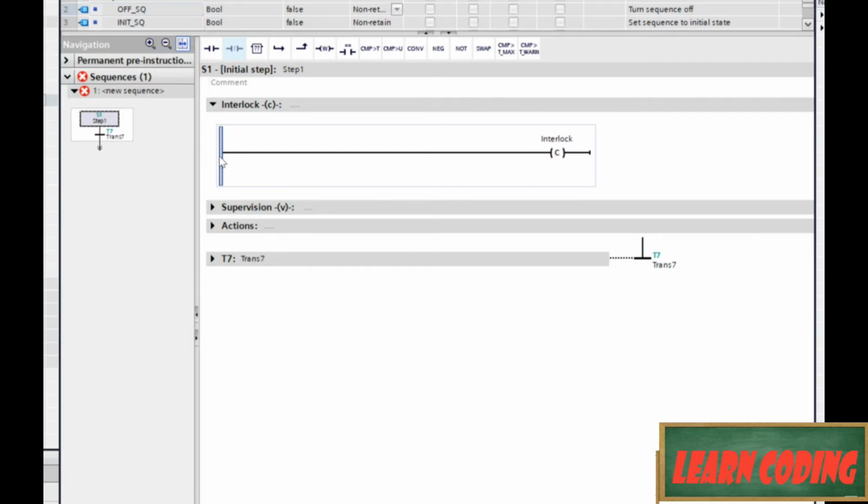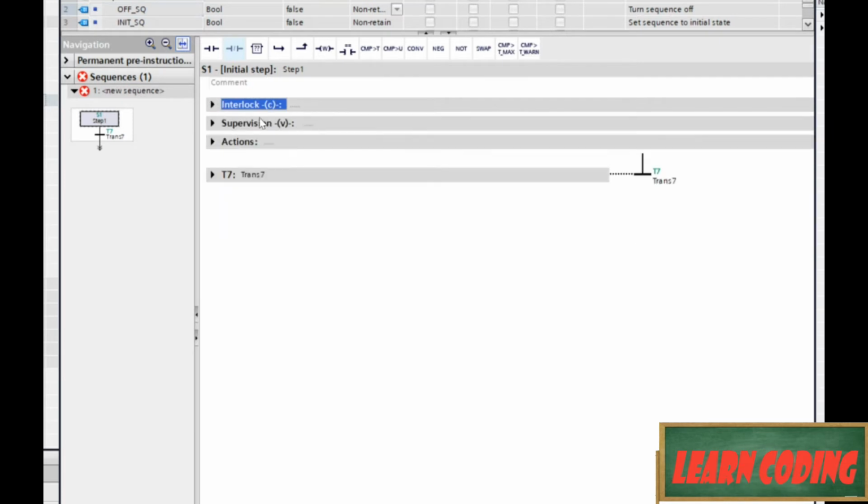Or we can just leave this rung empty right here, and then even if we're referring to this interlock for some things to start, this interlock is always going to be true as long as we don't have any conditions here. Sometimes we want to do it that way. We don't want to use an interlock. So, hey, we can just leave this alone and act like it doesn't even exist. Sometimes we do need an interlock, and we can drop the conditions here.